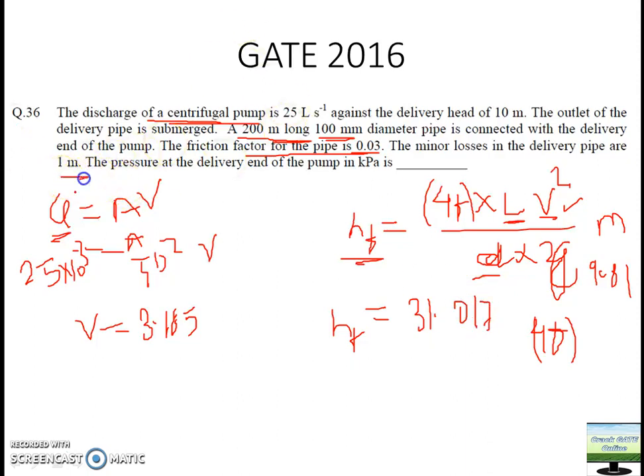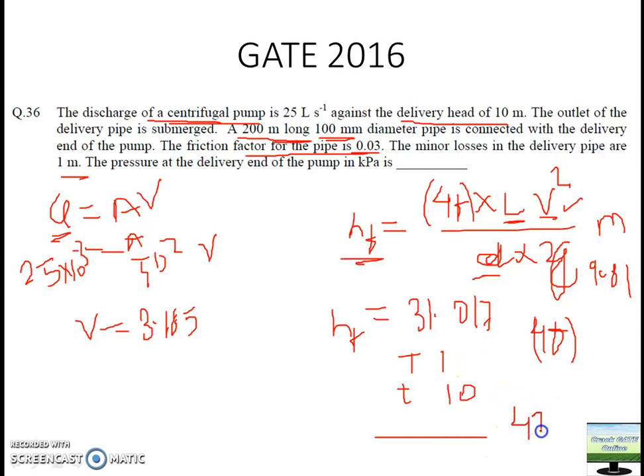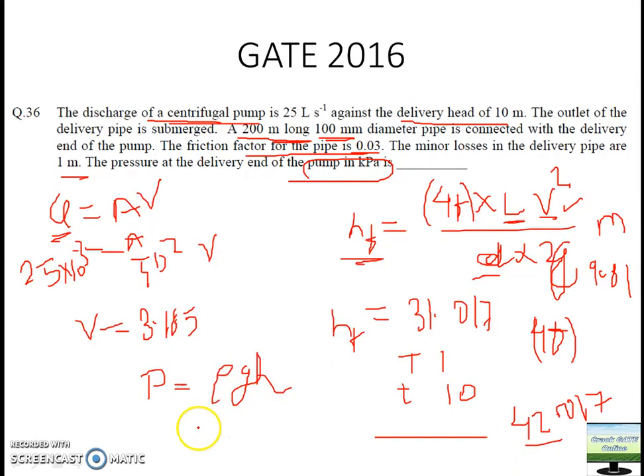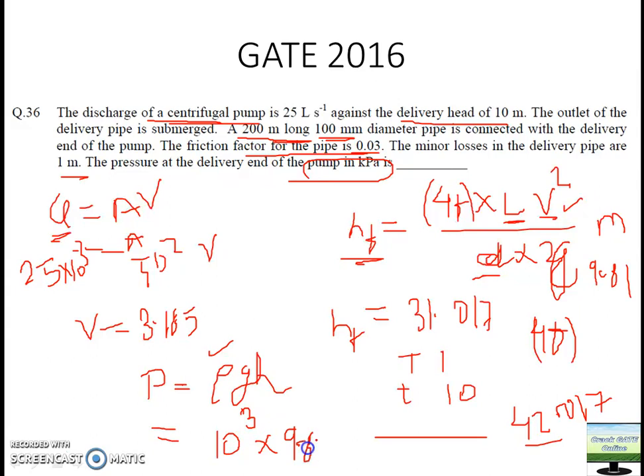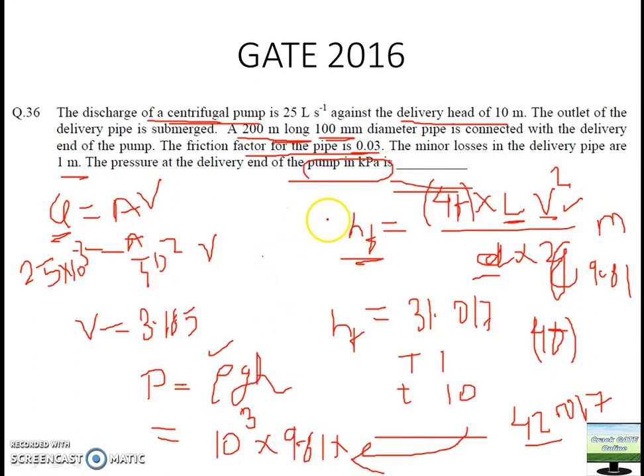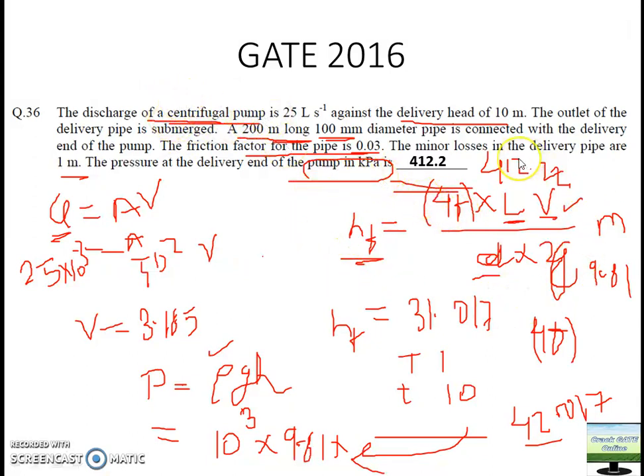Adding other losses of 1 meter and the delivery head of 10 meters, the total head becomes 42.017 meters. They are asking pump pressure, so pressure = ρgh = 1000 × 9.81 × 42.017. Converting to kilo-pascals, the answer is approximately 412.2 kPa. Here the centrifugal pump question is mixed with fluid mechanics — you find the total head and then calculate the pump pressure.